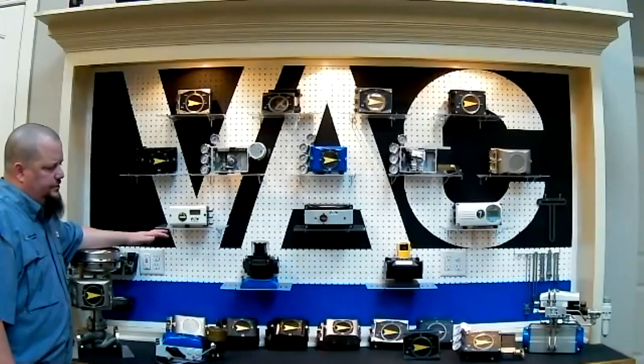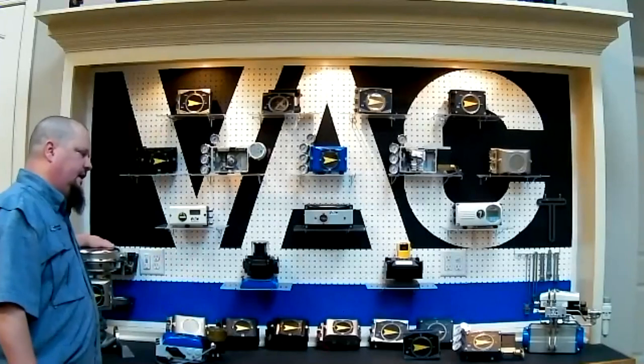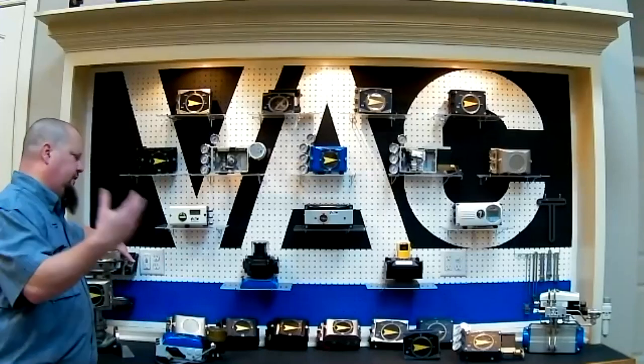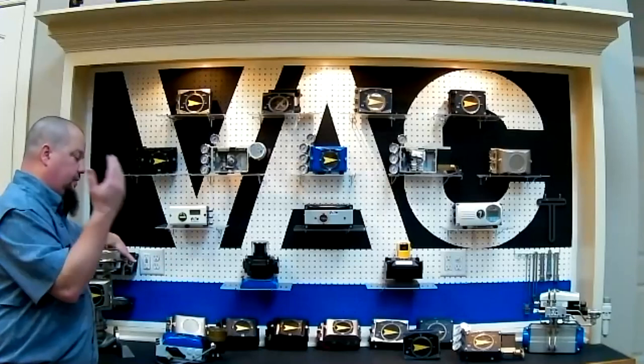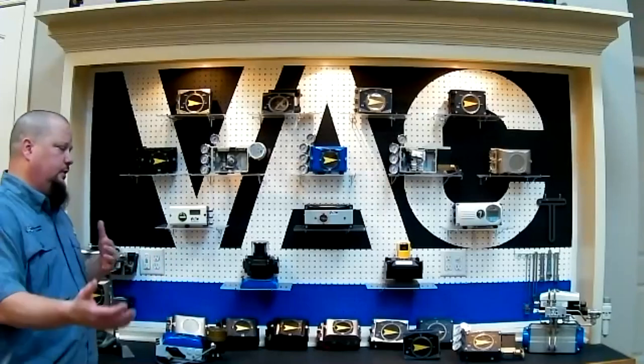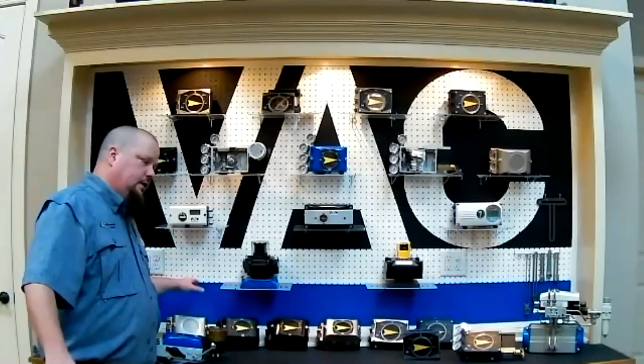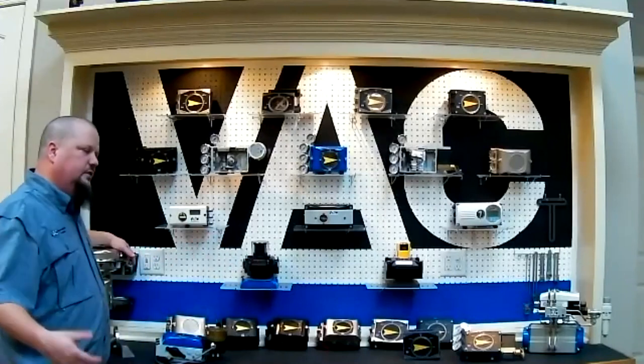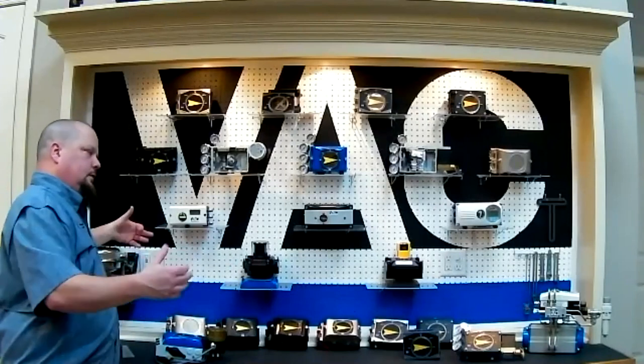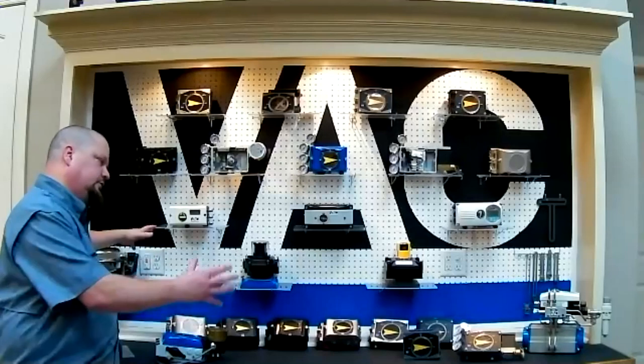Again, guys, most of the units on here are not going to be the positioner you sell all the time, or what you're going to look at supplying anytime. These fit little niches and fix issues that a customer's having. If somebody's pressure washing and cutting these plugs off, or knocking the plugs out and filling them full of water, then we can look at a plug. If they're seeing paint issues, we can look at a nickel or a Tufram unit. If the temperature exceeds 185 degrees, we can go to the high temp. Low temp stuff we don't see a lot of, but it is an option that we have to get down to negative 58 degrees. If you just think in terms of standard 4 to 20 input, just regular atmosphere, these are not the units you'd want to use.